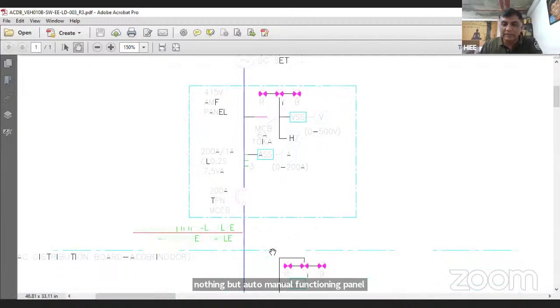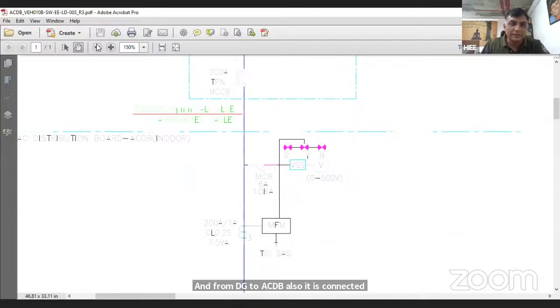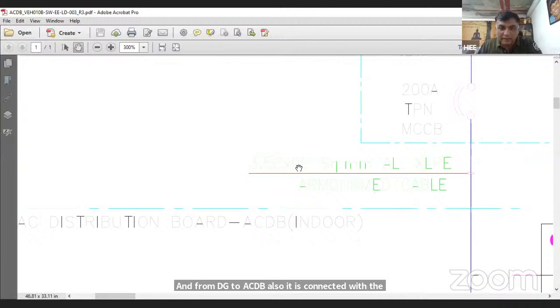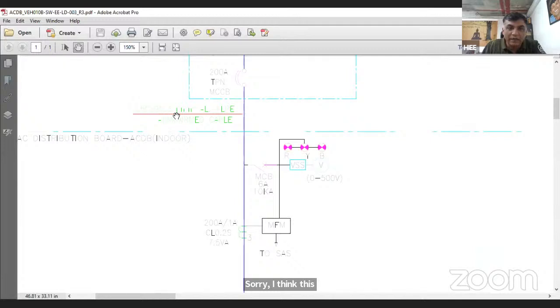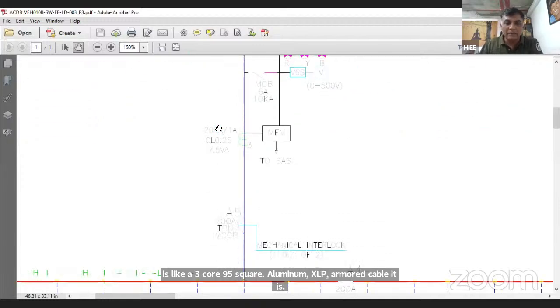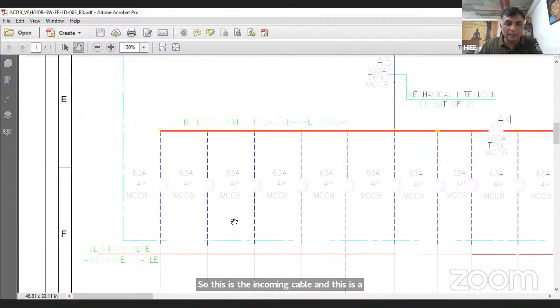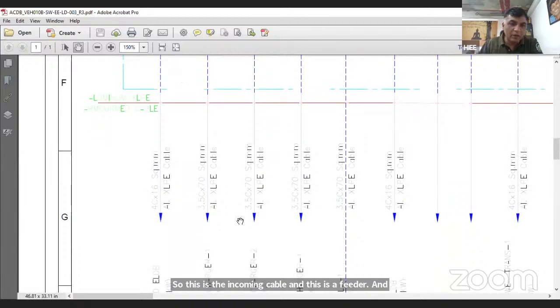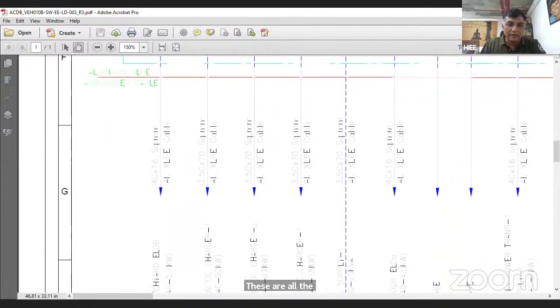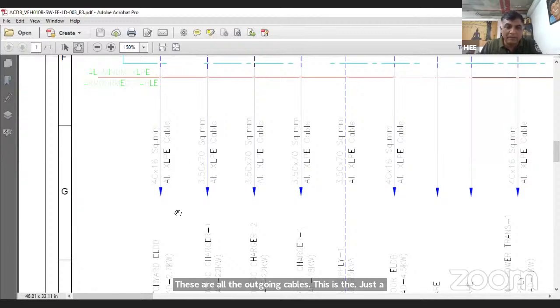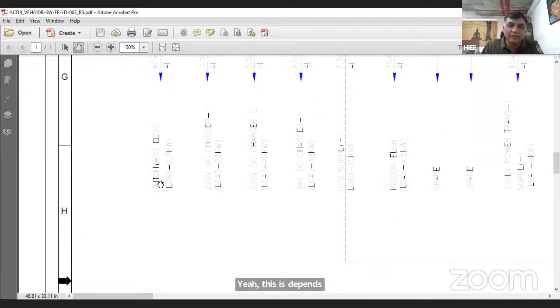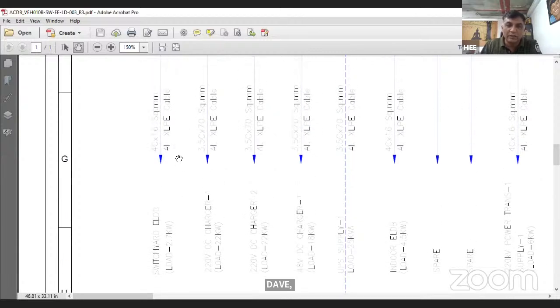And from the DG to the ACDB, it is also connected with, sorry guys, I think this is a 3-core 95 square mm aluminum XLPE armored cable. So this is an incoming cable and this is a feeder, and these are all the outgoing cables. It depends upon the connected feeder. Here we are going to connect the switchyard ELDB. ELDB is nothing but emergency lighting distribution board. The connected load is 2.7 kilowatt. For the 2.7 kilowatt load, we have connected a 4-core 16 square mm aluminum XLPE cable.